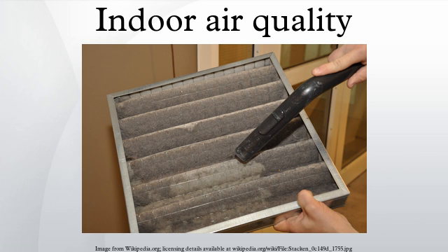For the past several years, there have been many debates among indoor air quality specialists about the proper definition of indoor air quality and specifically what constitutes acceptable indoor air quality. One way of quantitatively ensuring the health of indoor air is by the frequency of effective turnover of interior air by replacement with outside air. In the UK, for example, classrooms are required to have 2.5 outdoor air changes per hour. In halls, gym, dining, and physiotherapy spaces, the ventilation should be sufficient to limit carbon dioxide to 1,500 ppm.